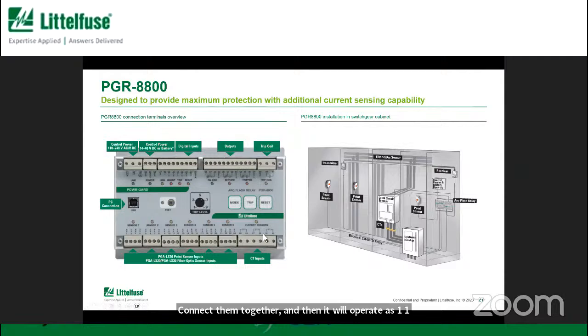But this relay has the ability to do the current transformer inputs. So this is the only one in the series that does that. So you can use light plus current if you wish. This product has 1 high-speed trip. So this trip coil in the top right is a 1 millisecond response time. It's an IGBT. And so this provides the 1 millisecond trip. We do have 3 other contacts here that can give you up to 4 independent zones. So what I mean is you can decide which sensor will trip which output if you wish. So it depends how complex the system you'd like it to be.